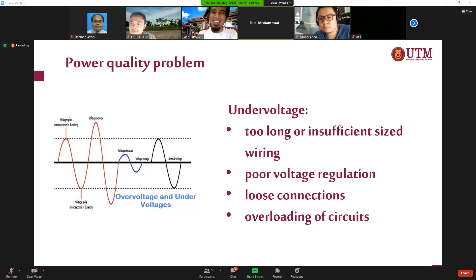Next, we are talking about over voltage. Over voltage might happen due to poor regulation from the power utility company at the distribution side, or due to a reactive power imbalance. We will discuss this with a case study on the next slide. So there are two problems that can cause over voltage: one due to poor regulation itself, the second due to reactive power imbalance.